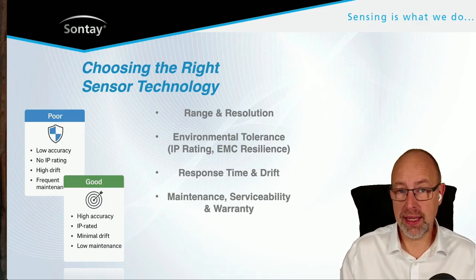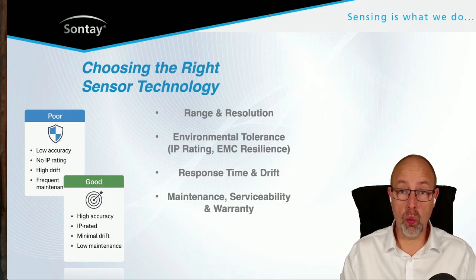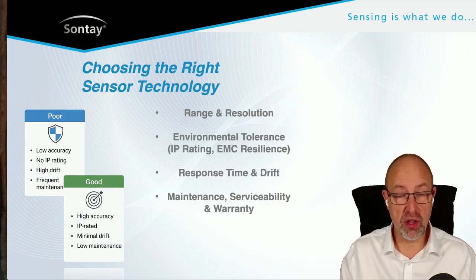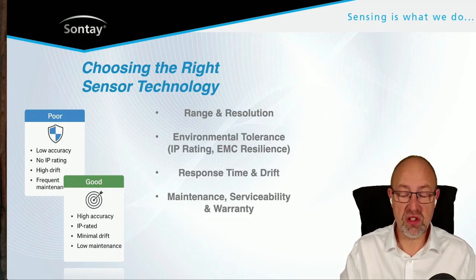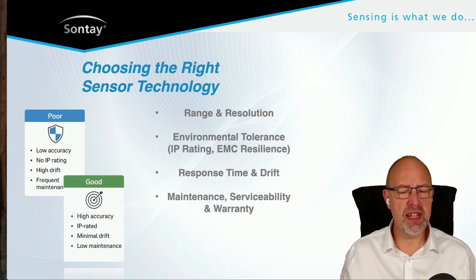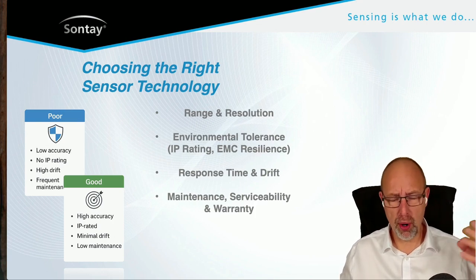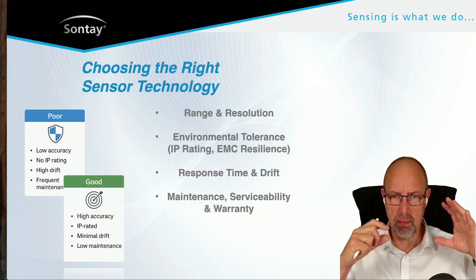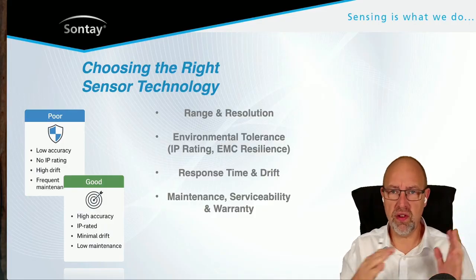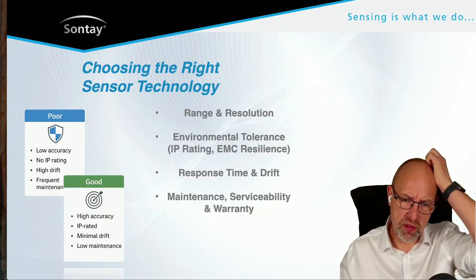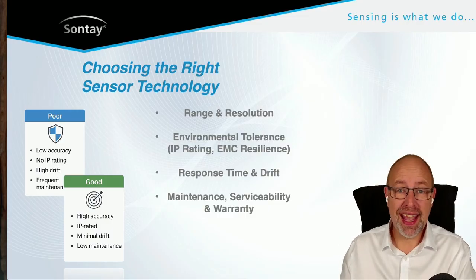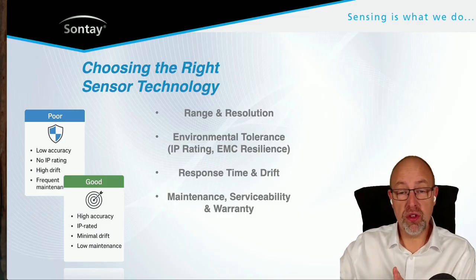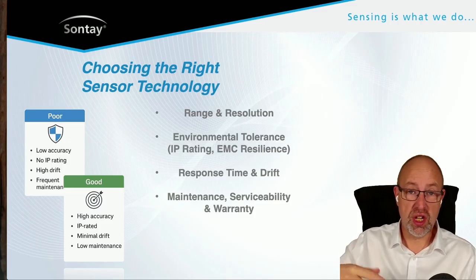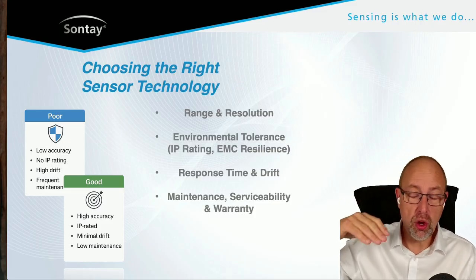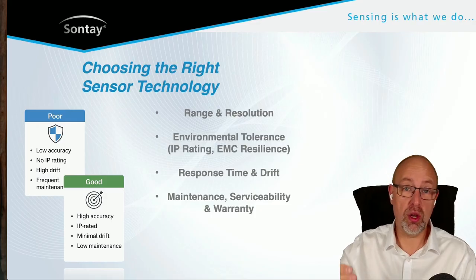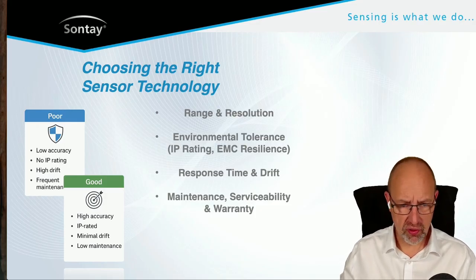Now, with electromagnetic compatibility, one of the things that we try to do to minimize the problem of electromagnetic interference is create distance. And you see this all the time. When we're installing BEMS, you don't put your control cables and your power cables next to each other because the electromagnetic interference can cause problems. In a data center, again, space is something that needs to be in there. If you've got a sensor which needs to sense a cold aisle, you don't want to put it next to a lot of fast switching equipment, which could cause interference.